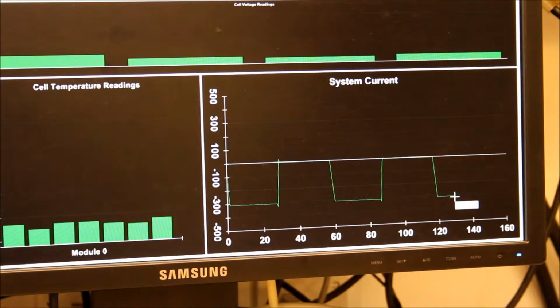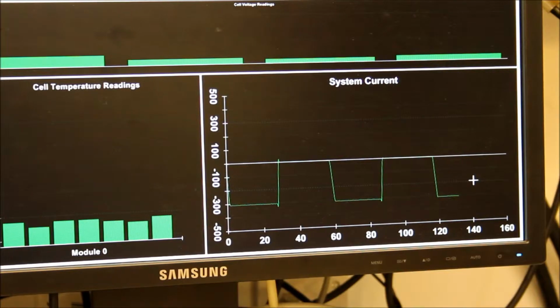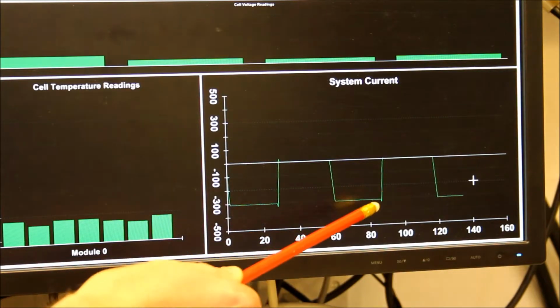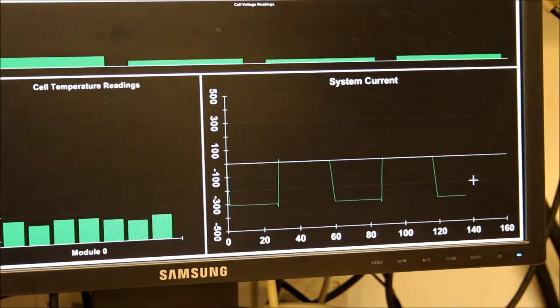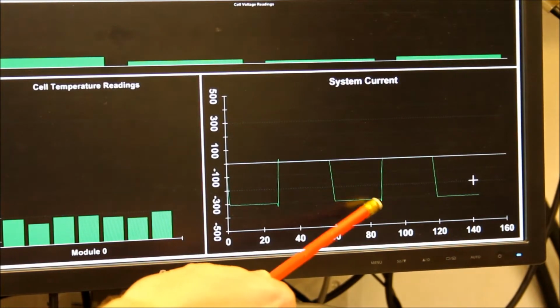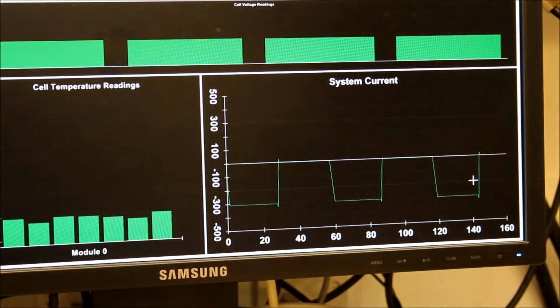So here we have the actual current that the battery is delivering at the moment, which we can see with our cursor here. And this is our third cycle, third repetition at 300 amps. So there's no current reduction by the BMS because the cells are still very far away from their maximum operating temperature, so the BMS sees no reason to reduce the current. Whereas previously, before we cleaned the contacts, we had to reduce current already on the second burst. So already here we were reducing, but certainly on the third.